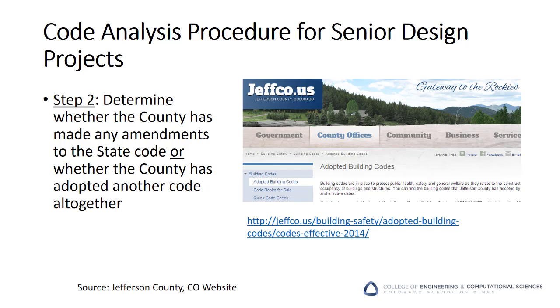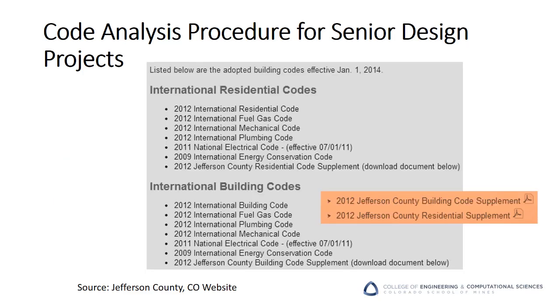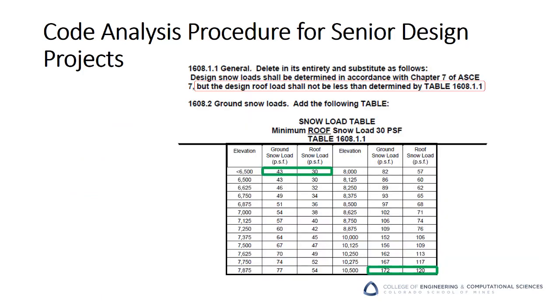It's important to determine if the county has made any amendments to the state code or adopted another code altogether. They have the authority, so go to the county website — in this case Jefferson County — and double-check the adopted building codes. It turns out that Jefferson County actually does have supplemental requirements for buildings and residential construction. One example is an addendum requiring a more stringent minimum snow load capacity. We probably get more snow than the average US location, and so the county wants to make sure structures can handle that increased local condition.